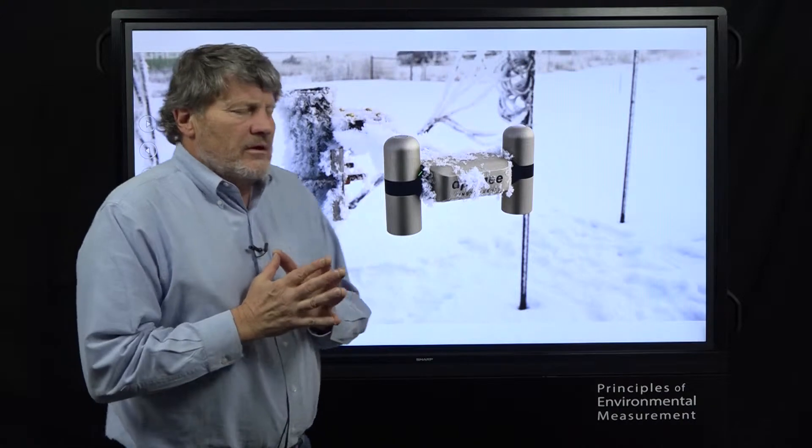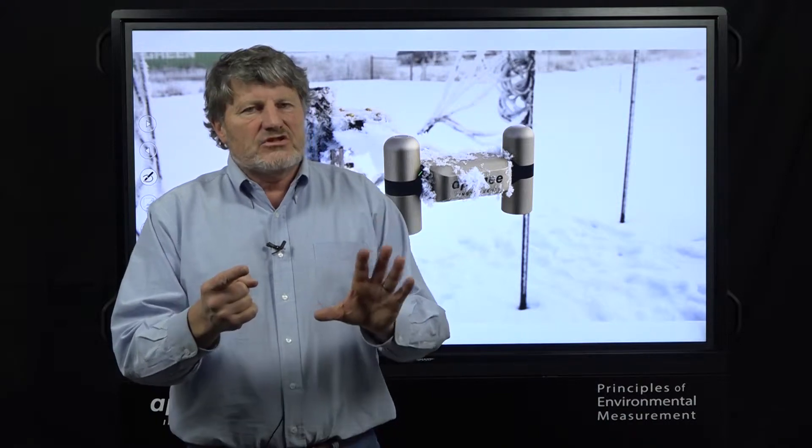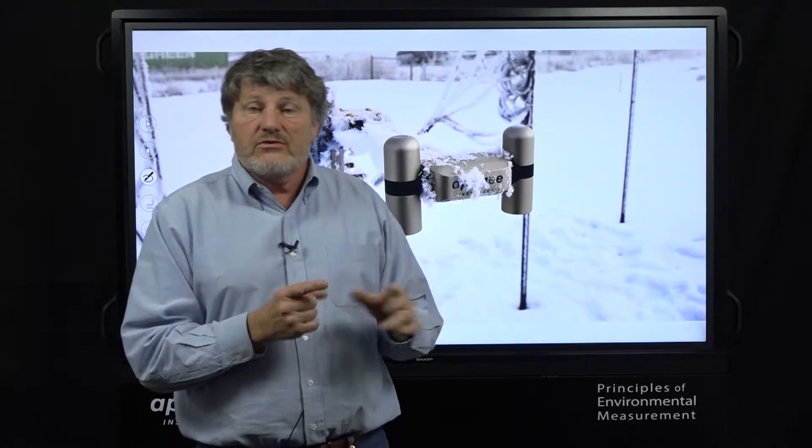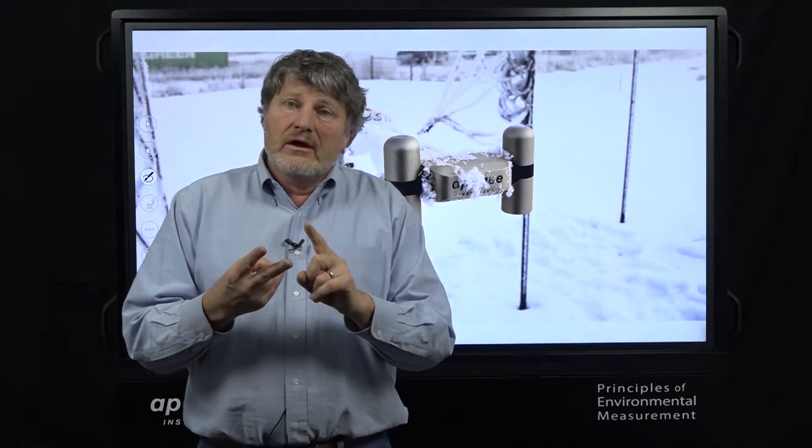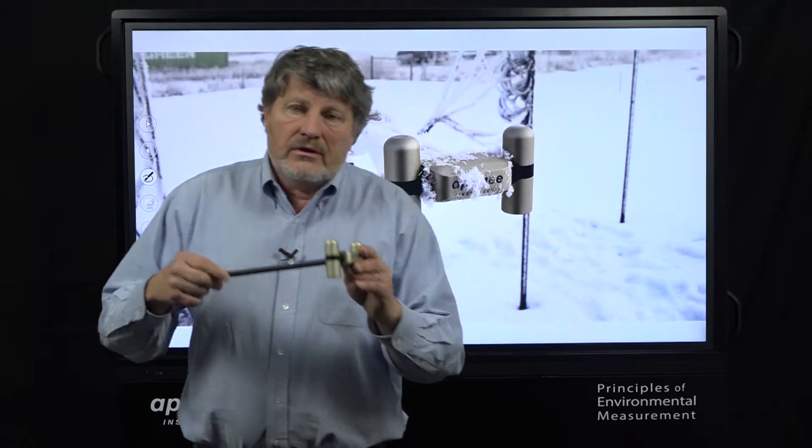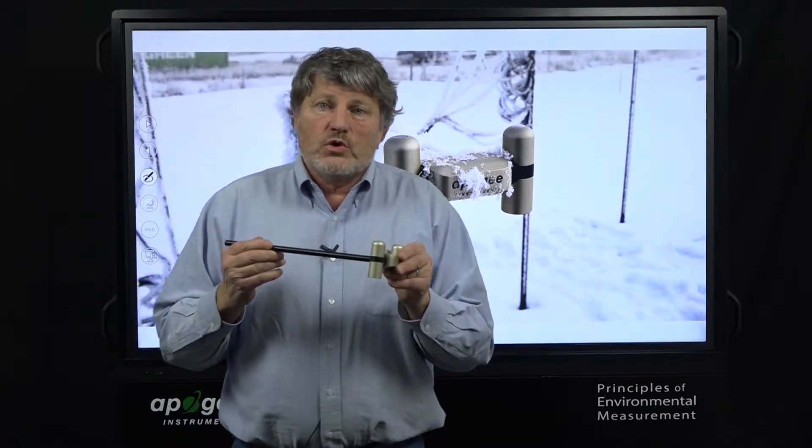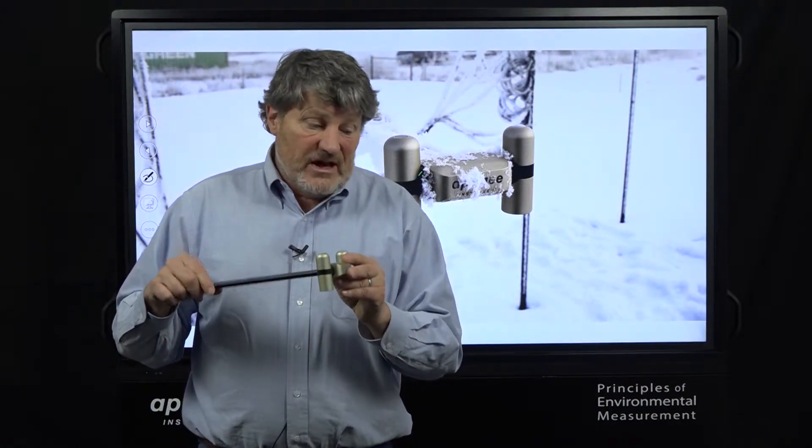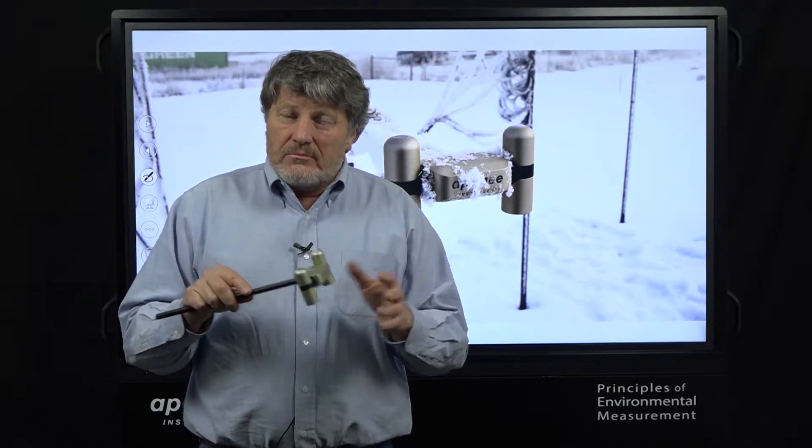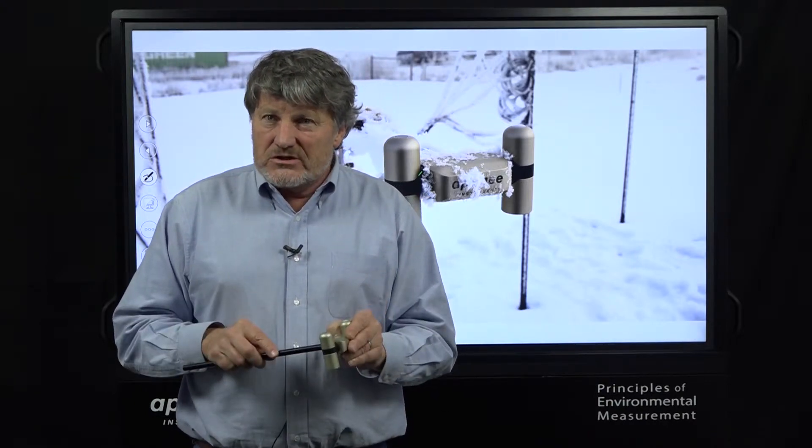So the big advantages are simpler to use. Fewer wires to hook up. Less consumption of all the wires on your data logger. You can use those other channels to measure other things with this. Much lower power requirements. And a small footprint. So it's easier to mount. And then finally, all of these are four-way net radiometers to get the best accuracy possible.